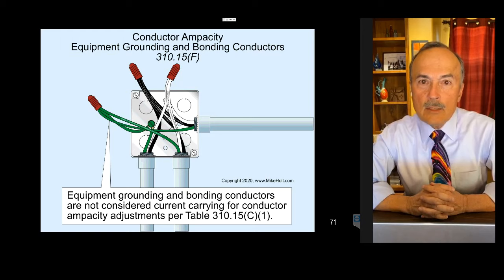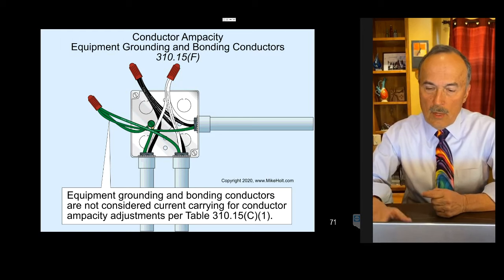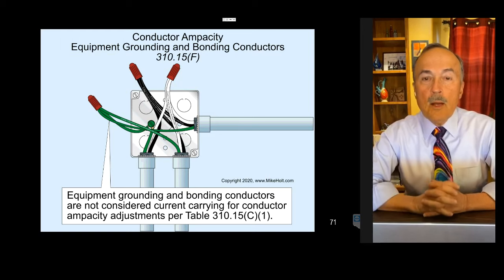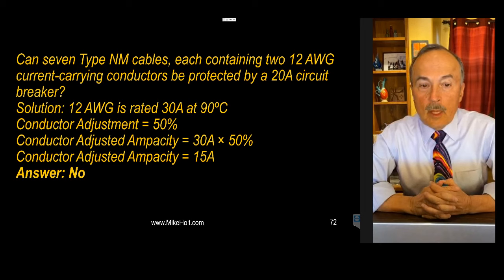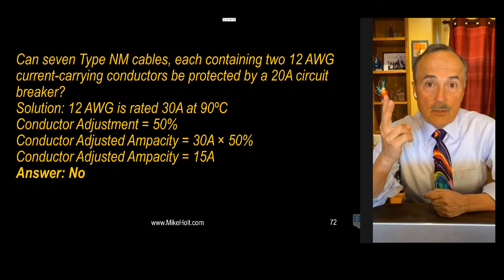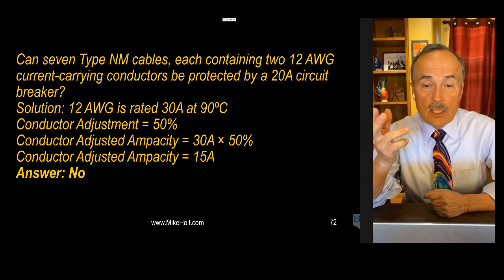And a question said, hey, Mike, my inspector said that you have to count the ground wire as a current carrying conductor. And I'm like, oh my gosh, you gotta be kidding me. 310.15F: no, an equipment grounding conductor is not a current carrying conductor, so we don't count equipment grounded conductors.